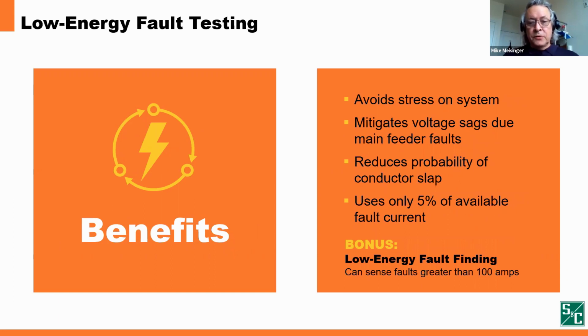Obviously, as you can see from the videos, we've avoided significant stress using low energy fault testing versus conventional reclosing. What you may not recognize, though, is that when we're using the low energy testing, the testing is virtually imperceptible to all the customers upstream of that fault interrupter. Consequently, because we're using less energy, we reduce the probability of conductor slap. You didn't see those jumpers that were moving so violently during the reclosing sequence moving at all while we were doing the low energy testing. And that's because we're using only roughly 5% of the available fault energy at that point on the system.